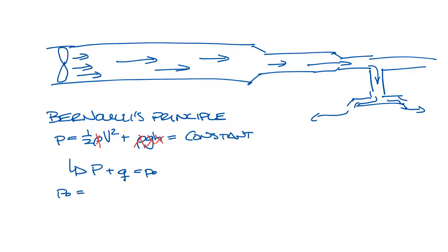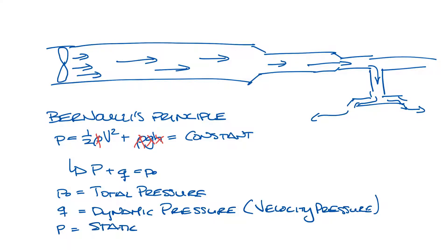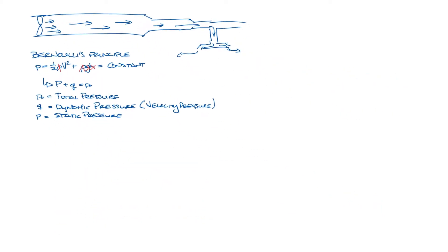P plus Q equals P naught. P naught is the total pressure. Q is the dynamic pressure, also known as velocity pressure. P is the static pressure. So now we have the equation Tp equals Vp plus Sp, or total pressure equals velocity pressure plus static pressure.